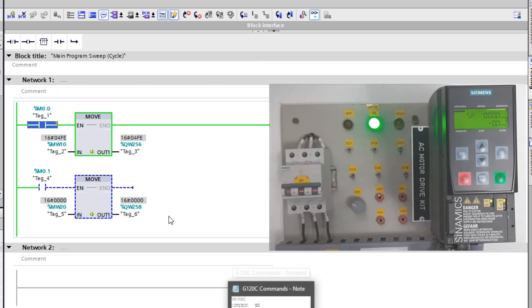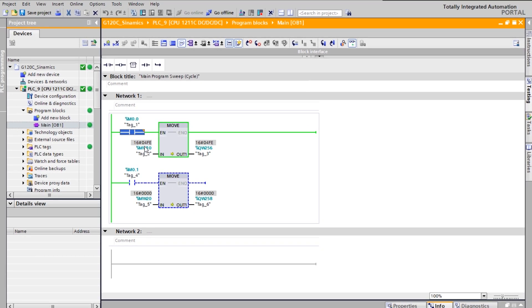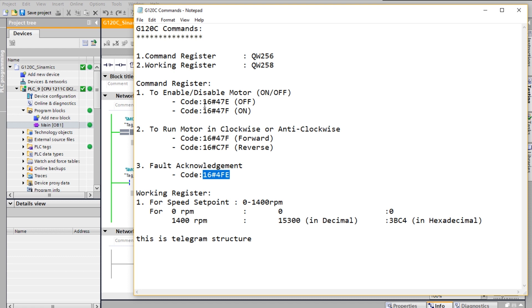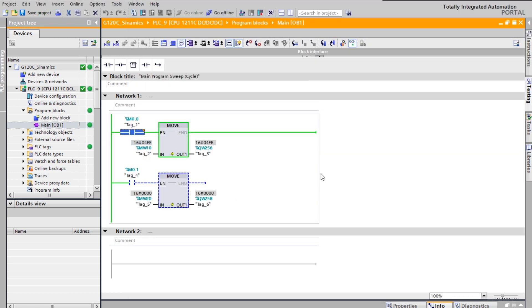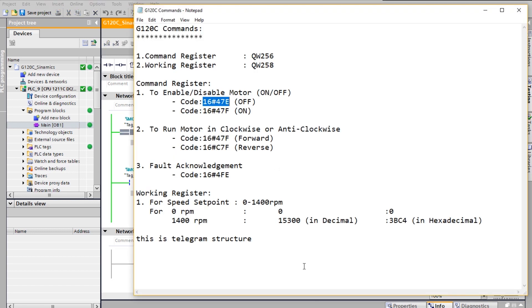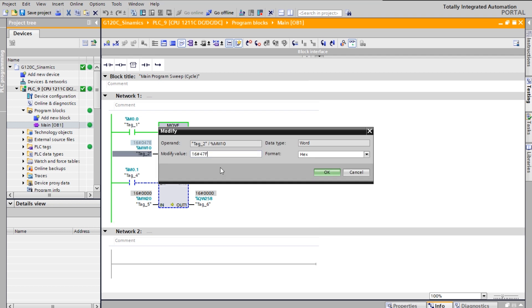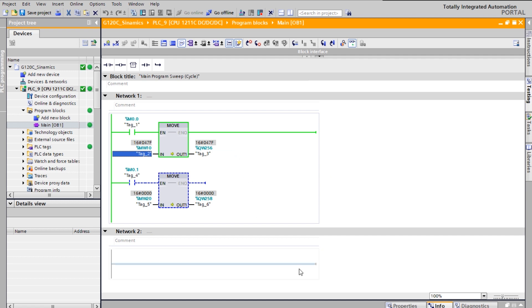Use this step only if there is a fault in your drive; if there is no fault, you can skip it. Now I want to clear the fault acknowledgement and make sure the motor configuration is stopped. I'm copying this code and pasting it, then clicking OK — the fault acknowledgement is cleared. Now I'm selecting the ON code to initiate the motor, and with this the motor will get initiated. Click OK; the motor is now waiting for the speed command.